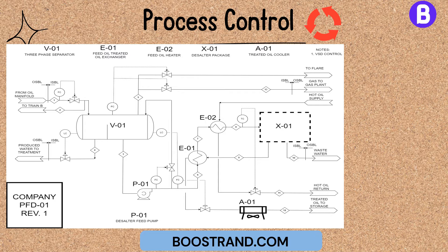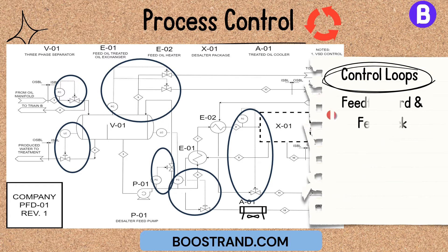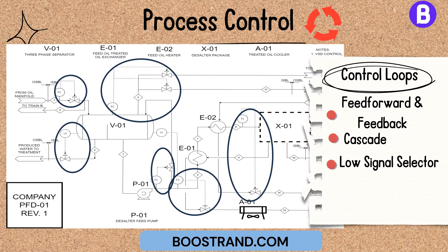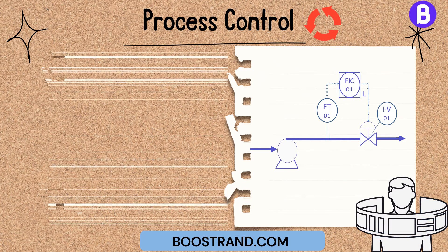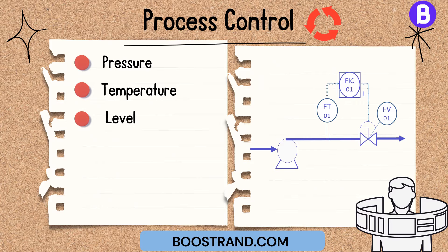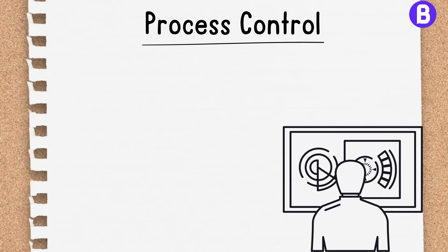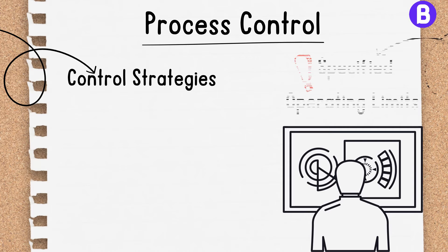In addition, a PFD shows the behavior of the control loop — whether it shall be feed-forward, feedback, cascade, or include a low signal selector, or a custom function such as summation of two flow sources or ratio control. A PFD goes beyond a flowsheet from simulation software by incorporating control loops, showing the process parameters to be controlled such as pressure, temperature, level, and flow rates. By choosing the optimum control parameter, the PFD assists in establishing effective control strategies to ensure the process operates within specified limits.